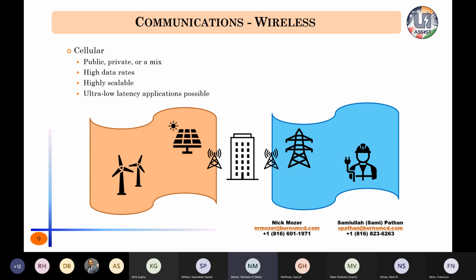So this means that you can go pick a user equipment, which is just an end device, say, for example, a cell modem that's mounted on a recloser pole or in a DER that can communicate back to the head end. And this device, because it has the LTE standard, is going to conform and behave in a way that can be interoperable with your other equipment on the network. So in other words, you're not just stuck with one type of vendor as you might be if you got, say, an MAS radio or a Zigbee radio.